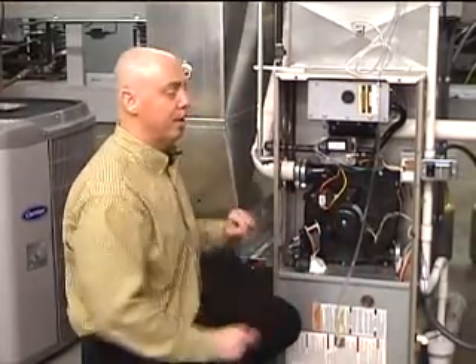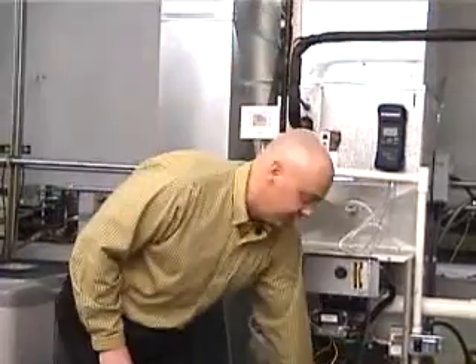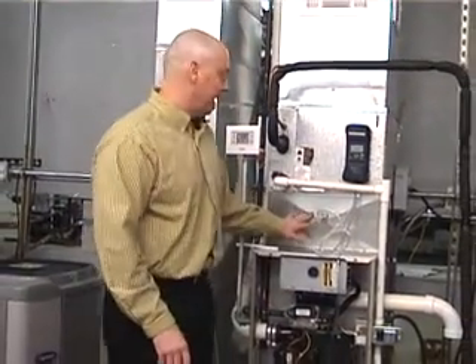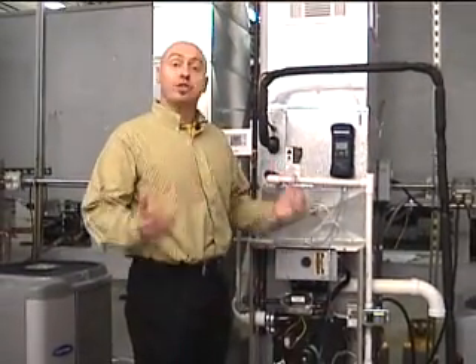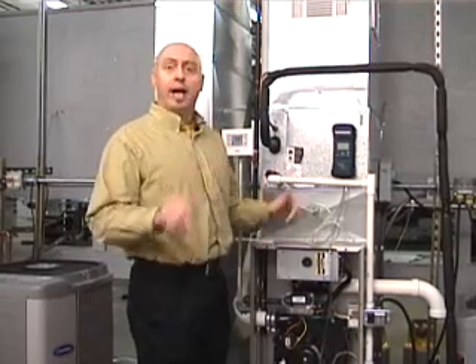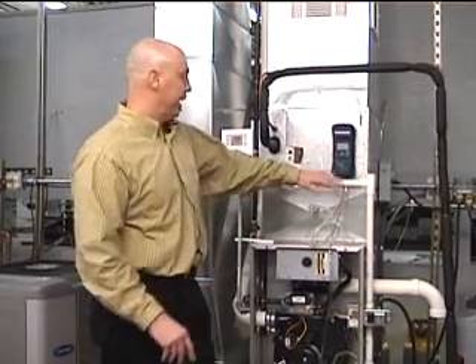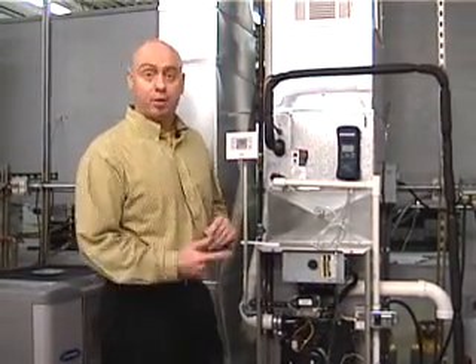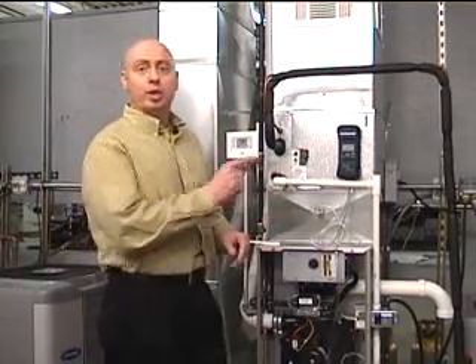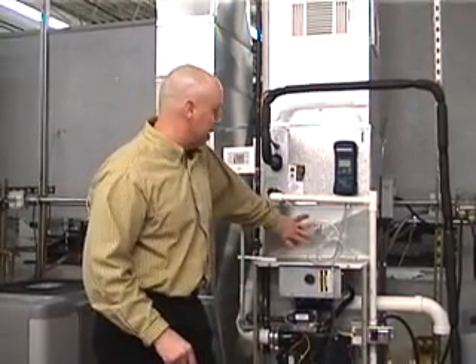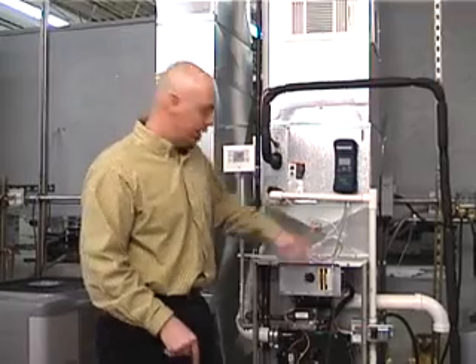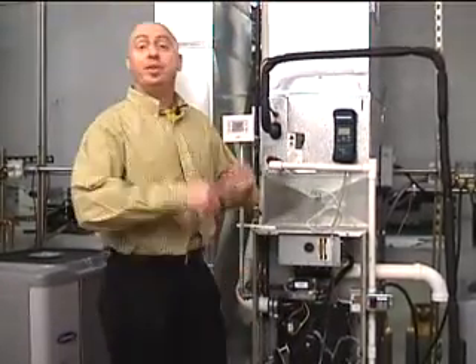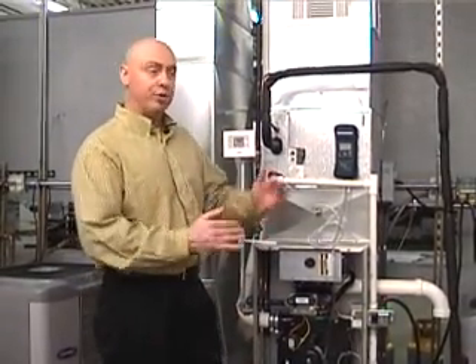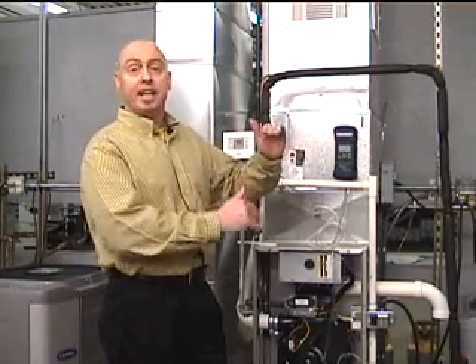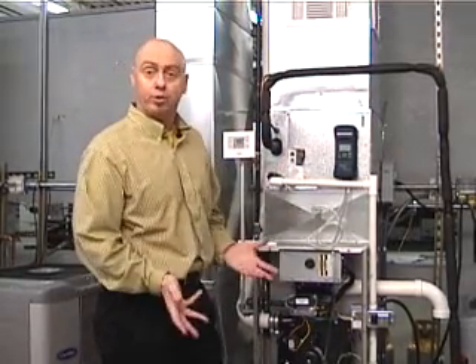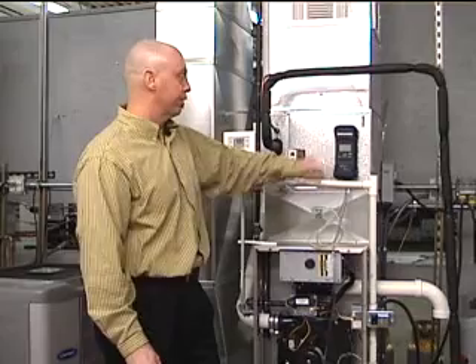So once I have those two numbers, this one is a negative number, this one is a positive number. When you take the total, or the sum, of the external static pressure, you add those numbers up. In this particular case, by using the Fyrite Pro, it does the math for you if you're bad at numbers. But you could do it one at a time. This number would be a positive number, this number down here will be a negative number. But when you take the sum or the total of the two, you forget about it being positive and negative. Just add the two numbers up, and that will give you your total. In this particular case, the meter does that for me.